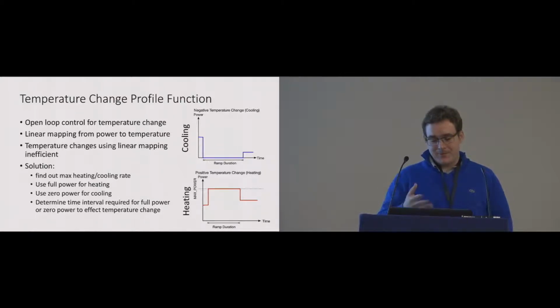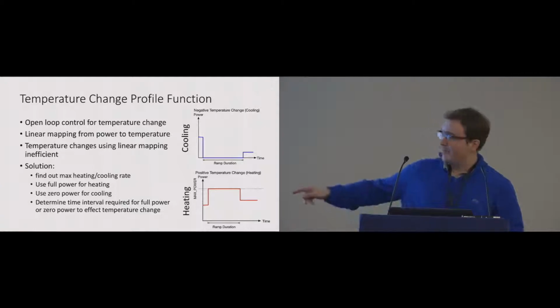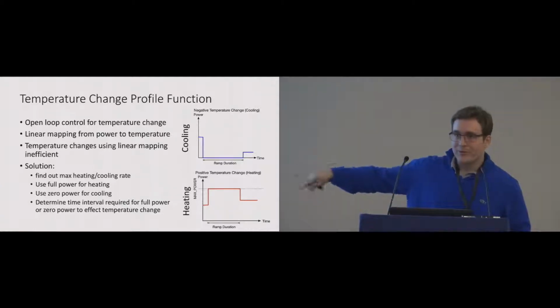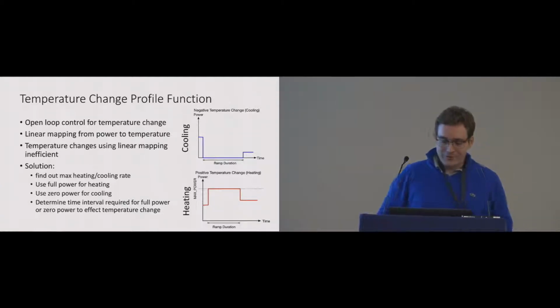So what we did is find out the maximum heating and cooling rate, and use full power for heating and zero power for cooling. Then we can determine the time interval required for full power or zero power to effect the temperature change as fast as possible, resulting in the power profile functions you see on the right.